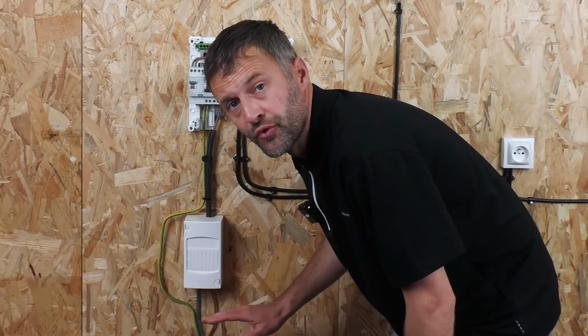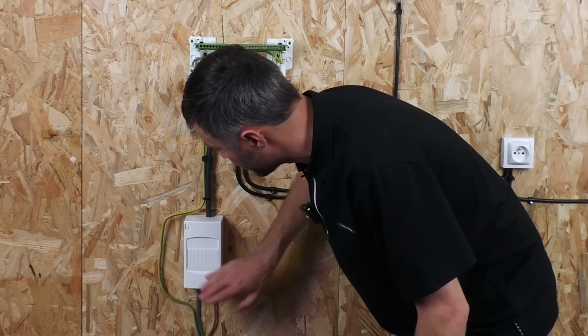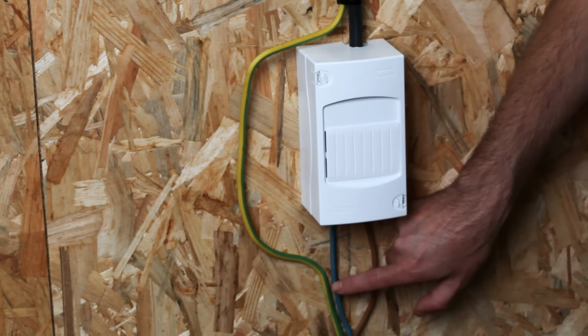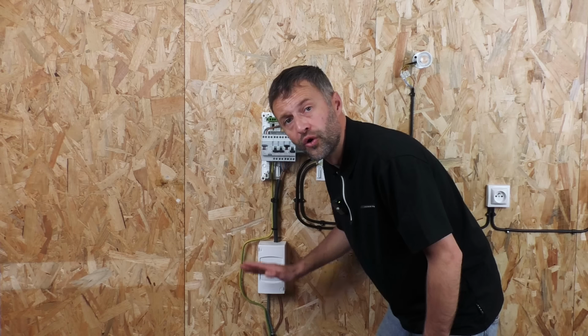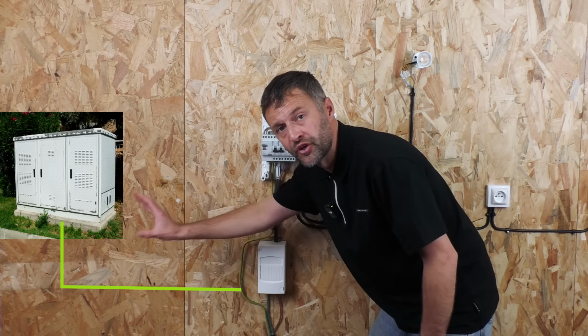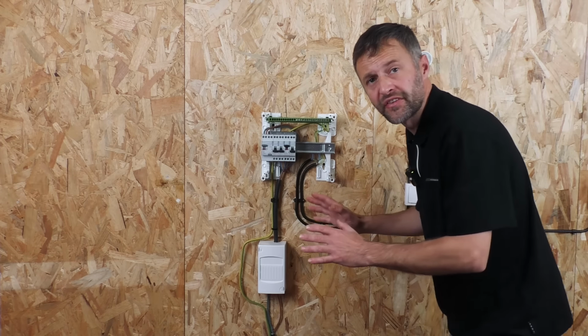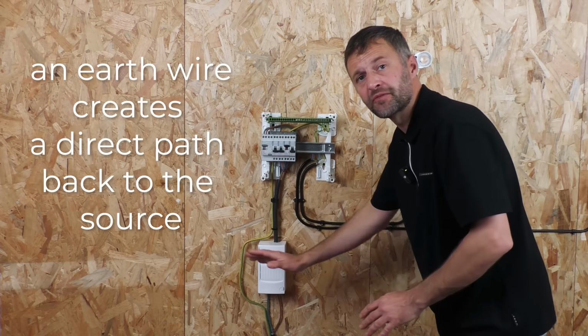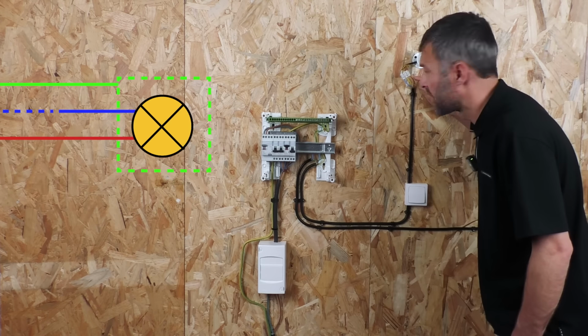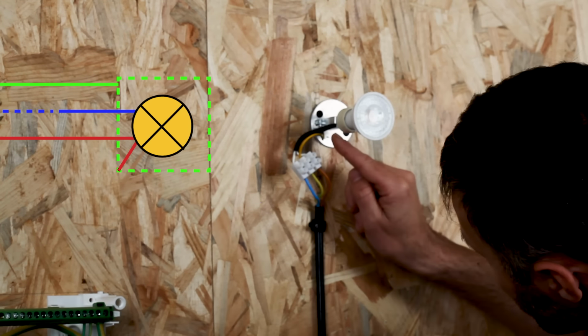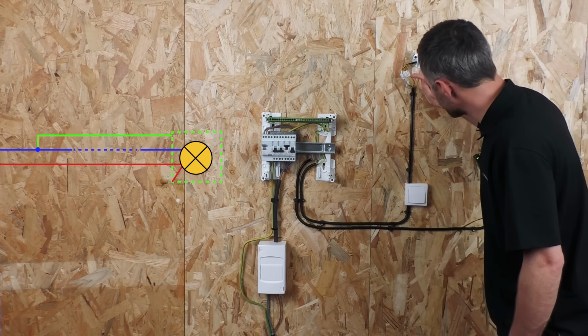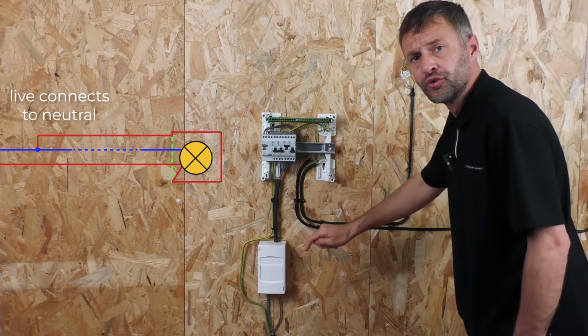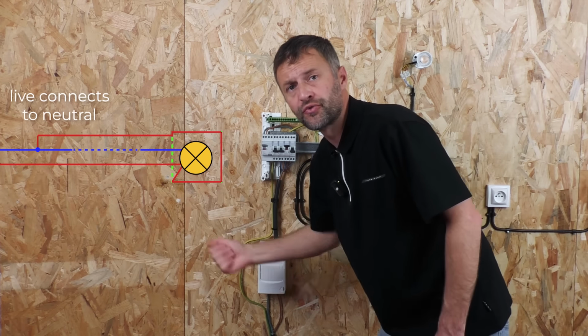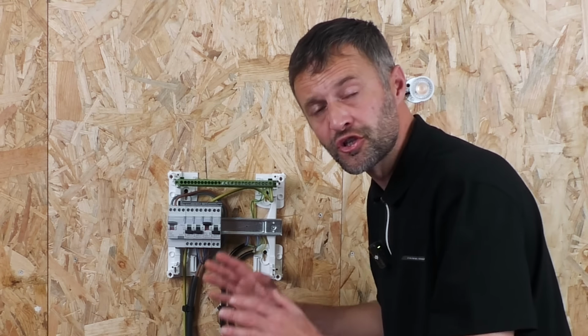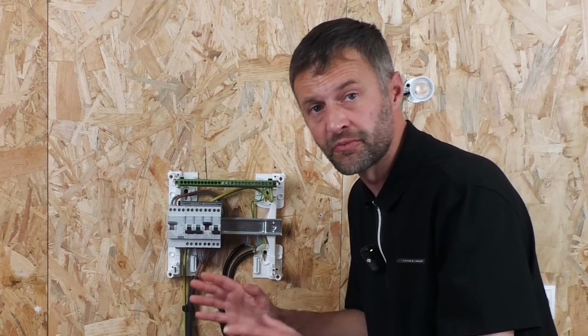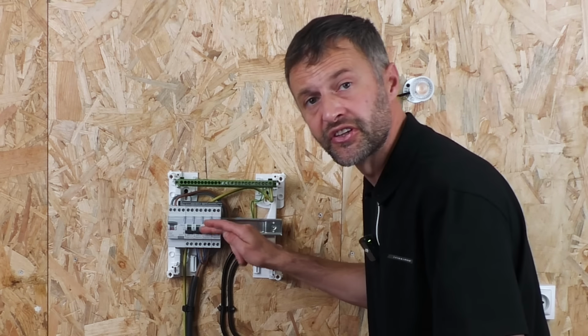Or it could be connected just before the meter. This box represents our meter. So the earth wire will be connected to neutral just here and wouldn't go any further. Or it could go all the way to the transformer and be connected to the neutral there. What matters is that this creates a direct path back to the source. So now if a live wire accidentally touches this metal, because maybe these thin wires are damaged, the current can return through the earth wire to the neutral and back to the source, to the transformer. And because this path has much lower resistance, the fault current will be extremely high and it will trip the circuit breaker instantly.